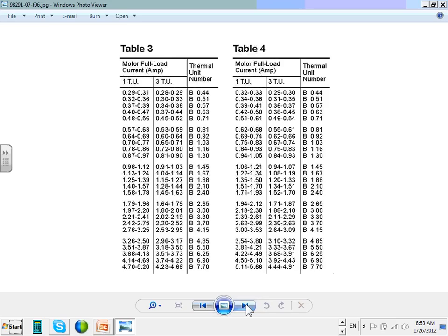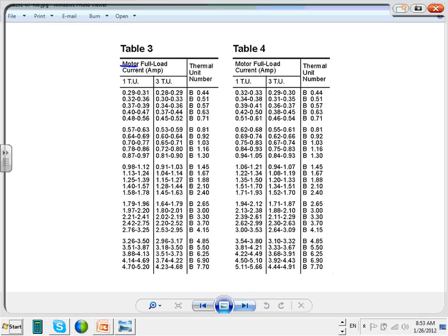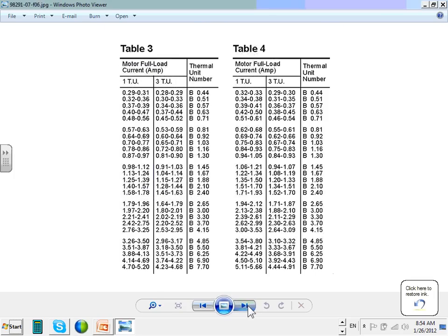It gives you 3 units. Say you have a full load motor. Look at this, this is your full load motor. This is for 3-phase, this is for single phase. So if I want to put a controller thermal unit heater, let's pick one little one randomly here. Take this, thermal unit number B2.40 can cover a full load amp of 1.45 all the way to 1.63. That's the range of full load amps that these can cover. When you size the heaters, you go buy one that covers the motor's amps. B2.40 will cover you between these 2 amps. I don't like to go over that one, at least with the designers.